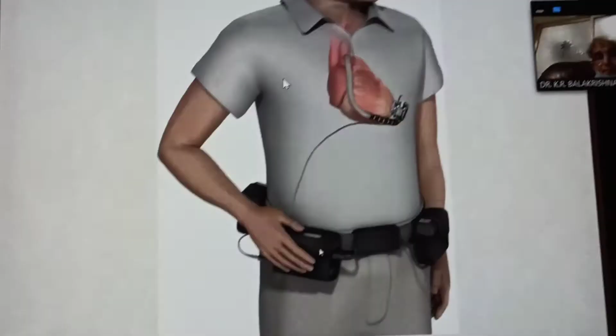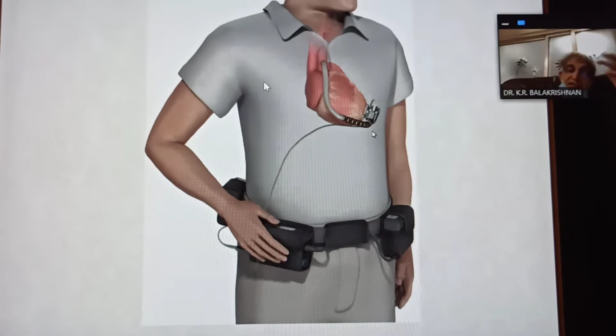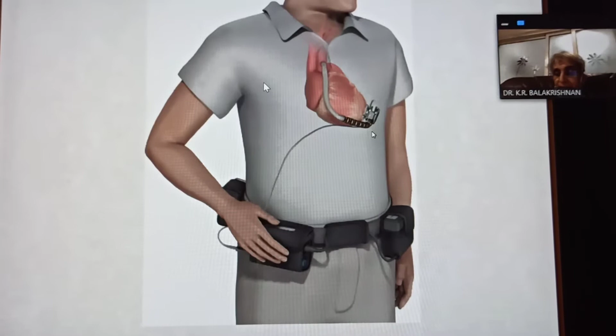But there are still some disadvantages of this, because when you have a cable coming out of the body, the exit site can get infected, especially in a hot and humid country like India, where in summer months you need to take a shower several times in a day. And each time you take a shower, you need to make sure that the exit site doesn't get wet. So you need to wrap yourself up with plastic gear that the company provides. But it's not really that cumbersome. So now there have been some recent advances. Notably, an Israeli company has come with a mechanism by which these pumps can be powered transcutaneously without breaching the skin barrier, which gives you the possibility that you don't have anything which is outside and is completely implantable. It's still not universally available, but I expect in the next couple of years that technology will come in.